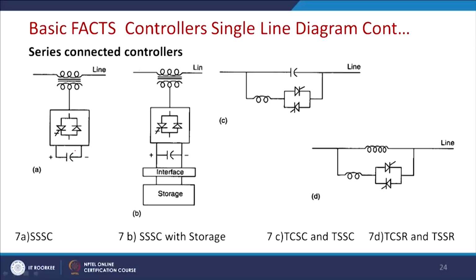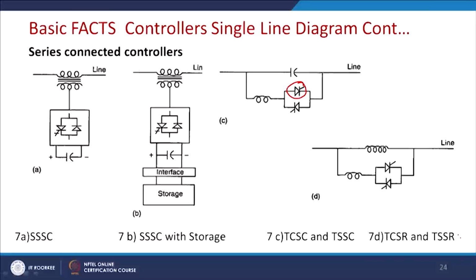In the same way, this SSSC can come with storage devices, so it can inject voltage and current in phase and quadrature, and it is quite a versatile device as far as series compensation is concerned. TCSC essentially deals with the variable impedance component. By changing the triggering angle of the thyristor, the impedance can be controlled, and thus you can control the impedance of the line in the transmission system. In the same way, if you have a TCR, we will have this kind of system. Please note that the thyristor should be connected in the line where an inductor is connected. We cannot connect a thyristor in series with a capacitor. Why is it so? I leave this question to the students.